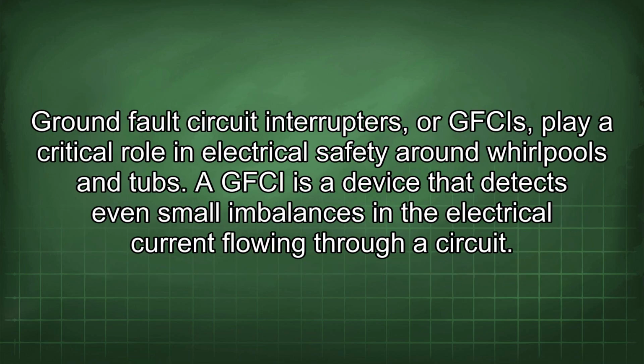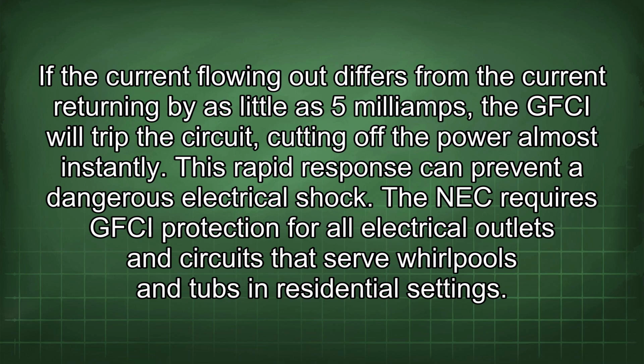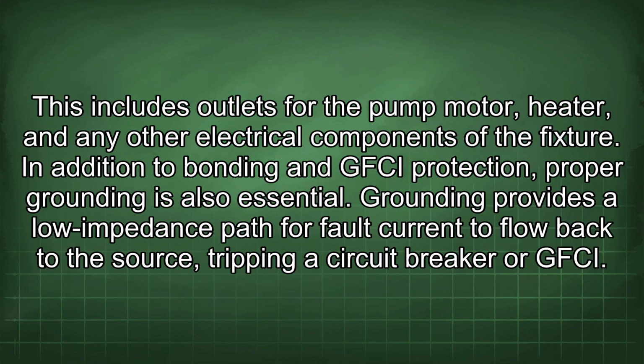Ground fault circuit interrupters, or GFCIs, play a critical role in electrical safety around whirlpools and tubs. A GFCI is a device that detects even small imbalances in the electrical current flowing through a circuit. If the current flowing out differs from the current returning by as little as 5 mA, the GFCI will trip the circuit, cutting off the power almost instantly. This rapid response can prevent a dangerous electrical shock. The NEC requires GFCI protection for all electrical outlets and circuits that serve whirlpools and tubs in residential settings. This includes outlets for the pump motor, heater, and any other electrical components of the fixture.